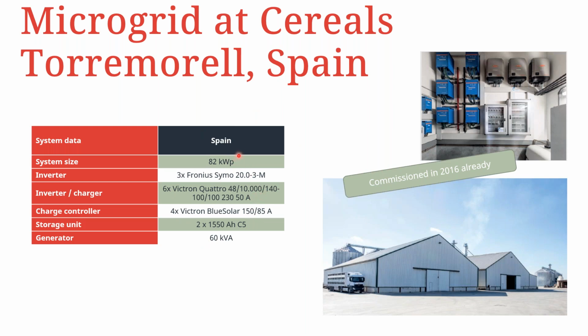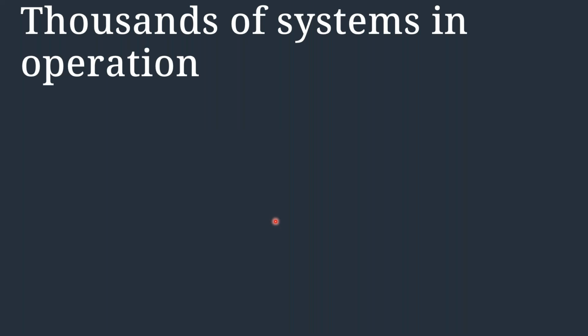This is one of the examples, an 82 kilowatt peak system in Spain. It is using 3 Fronius Symo 20 inverters with 6 Victron Quattros. It also has 4 Blue Solar Victron chargers, 150/85. And in addition to the battery storage, it also incorporates a diesel generator, in this case 60 kVA.